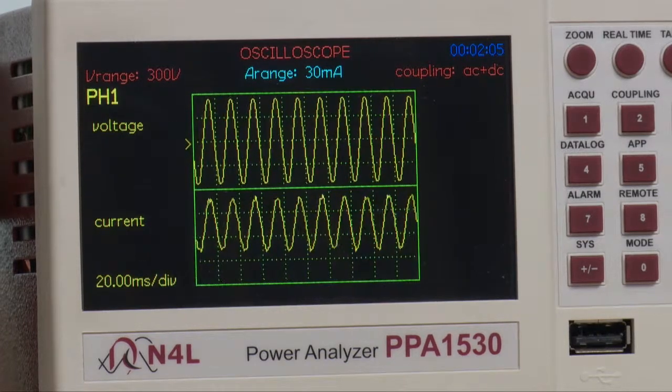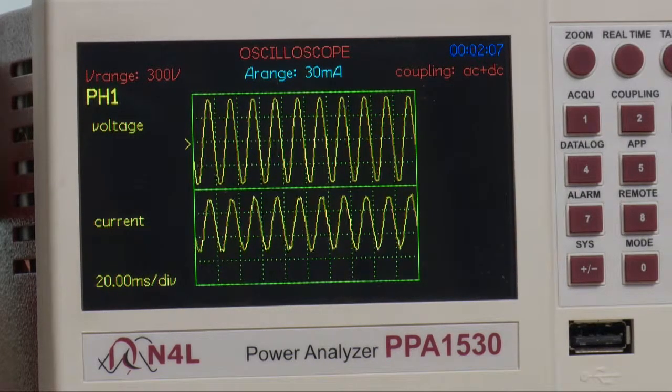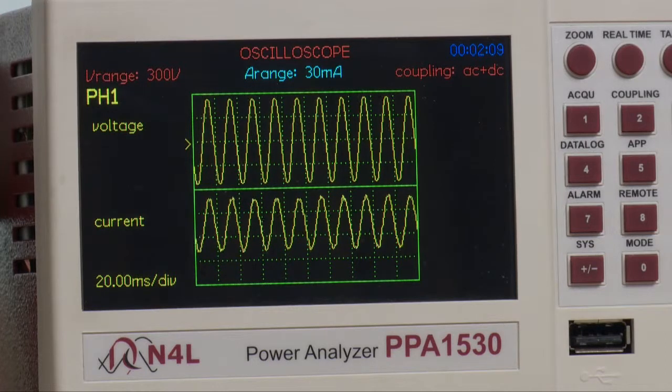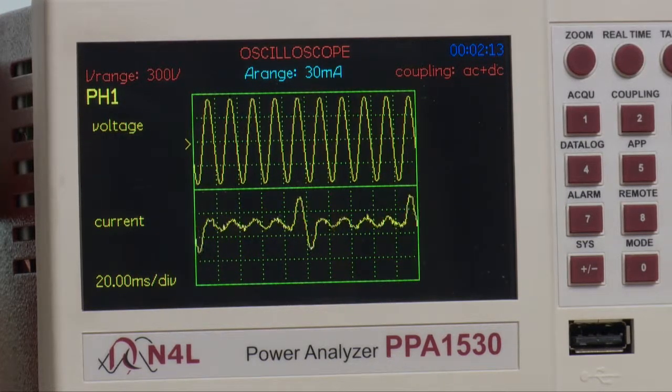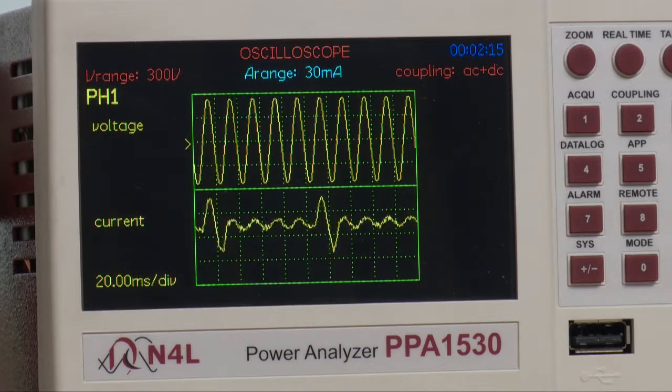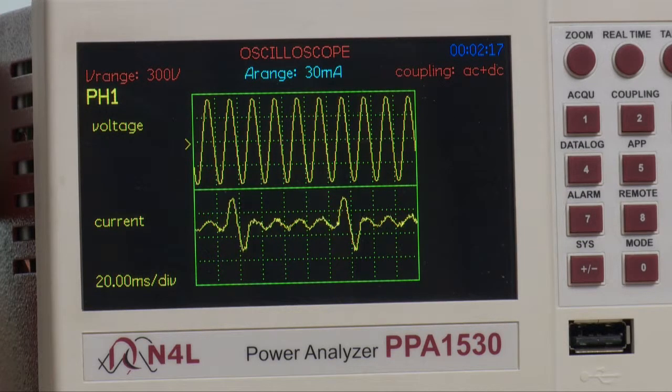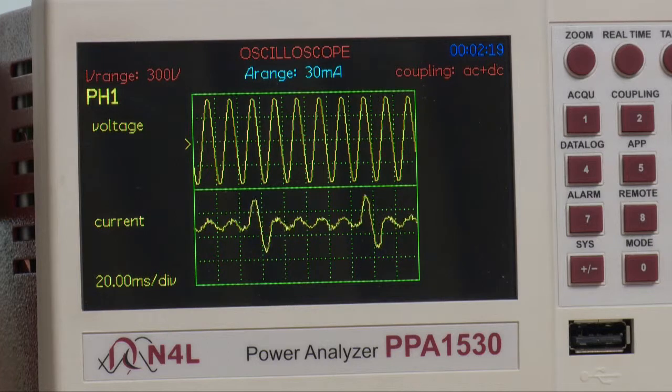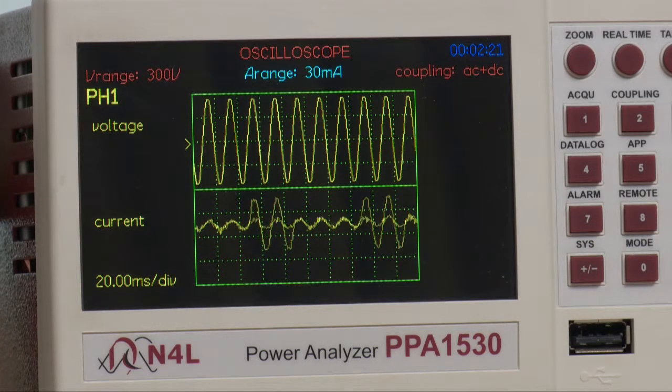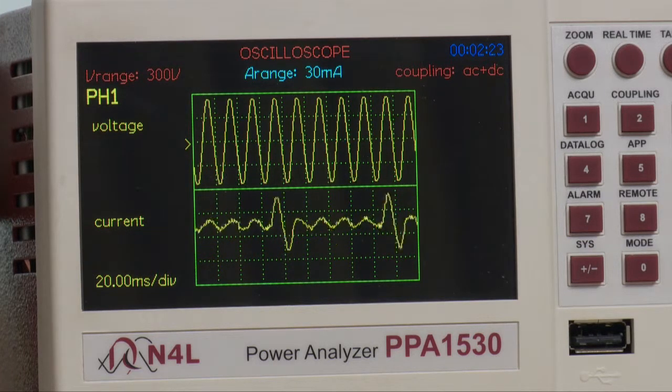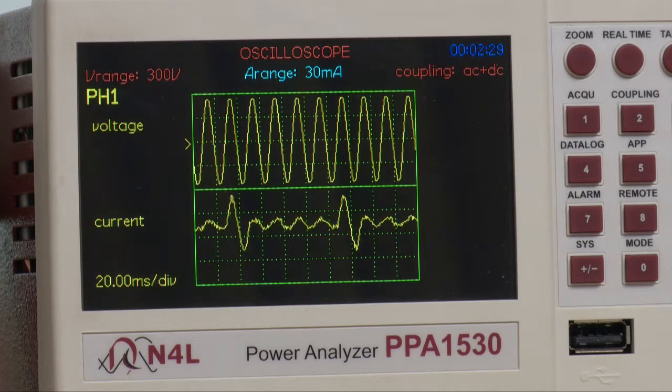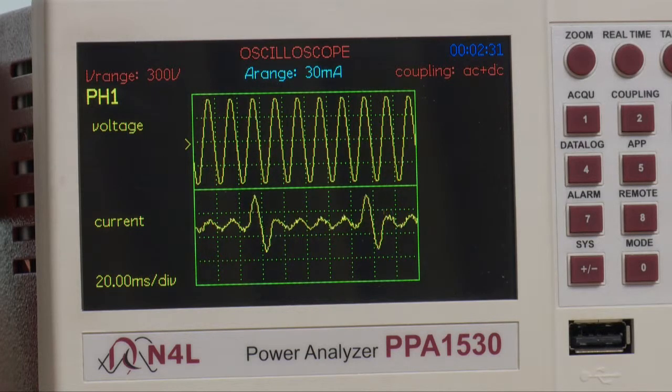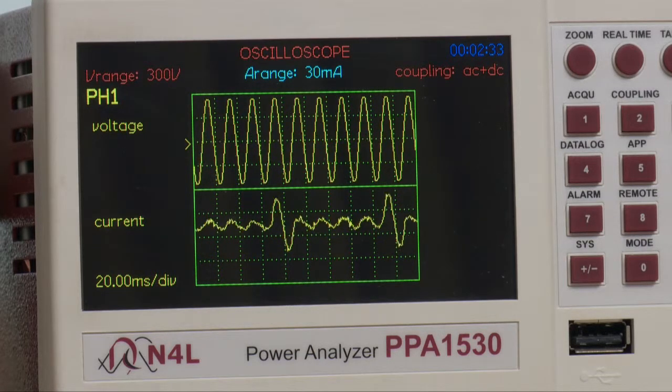If we now go back to the oscilloscope mode, we want to illustrate a particular problem associated with standby power, and that is the low-duty cycle pulses of current. This is where a standby power supply will take a trickle current, followed by periodic pulses of current, to charge the input stage during standby mode. This is a particular problem for power analyzers because it causes a problem for frequency detection and ranging, and the power will tend to pulse.